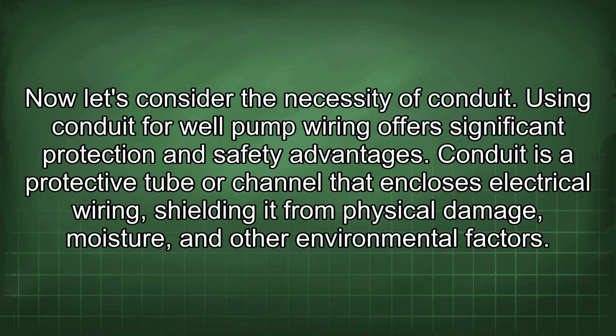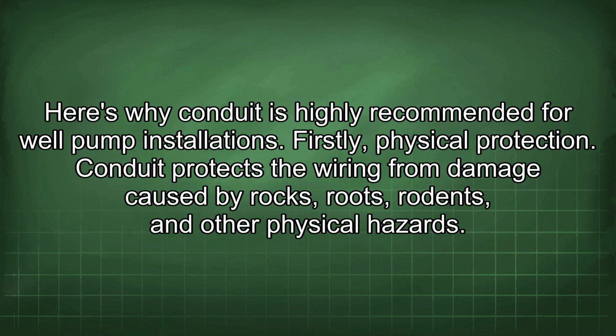Now let's consider the necessity of conduit. Using conduit for well pump wiring offers significant protection and safety advantages. Conduit is a protective tube or channel that encloses electrical wiring, shielding it from physical damage, moisture, and other environmental factors. Here's why conduit is highly recommended for well pump installations. Firstly, physical protection. Conduit protects the wiring from damage caused by rocks, roots, rodents, and other physical hazards.